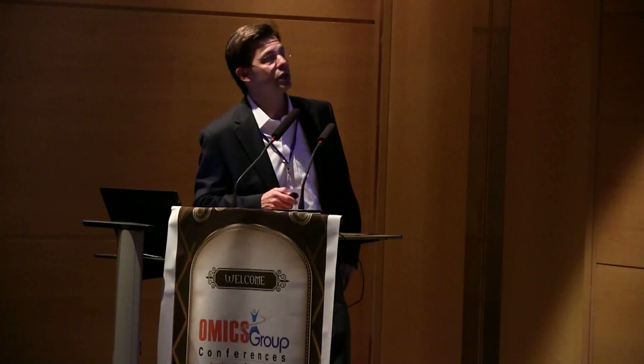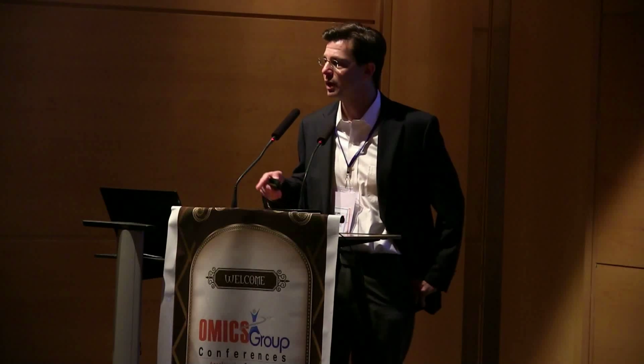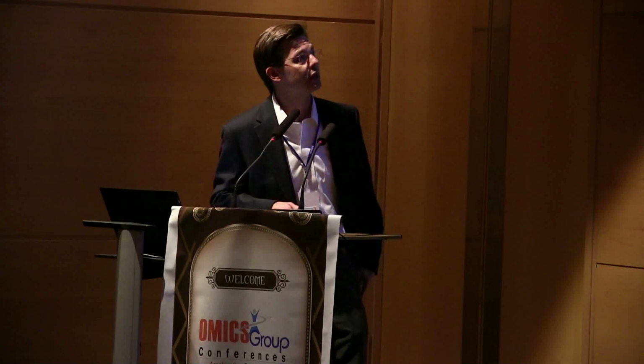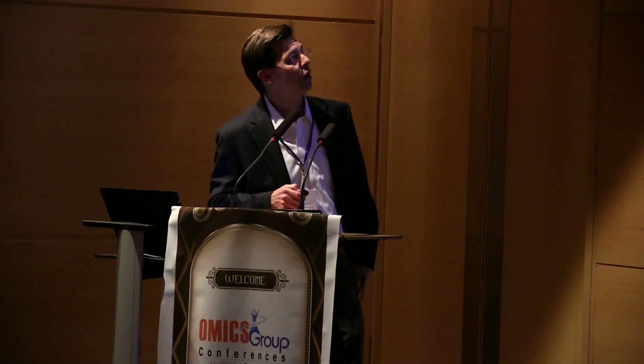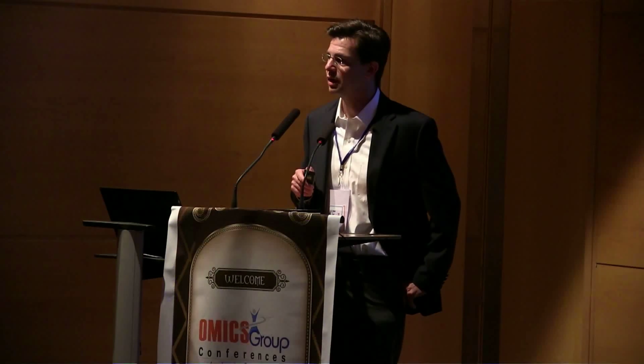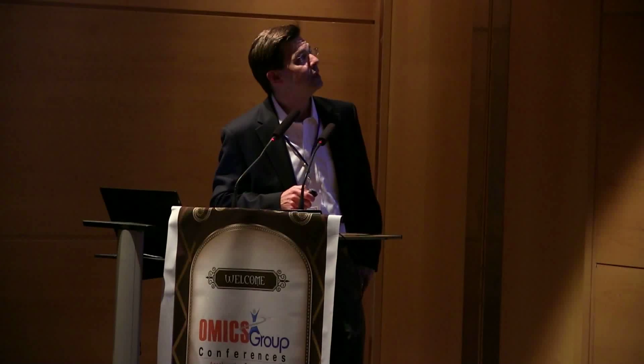So here's the Micron Jet. It's made by a company called Nanopass Technologies, and Yoram Levin is the CEO of Nanopass. We've worked closely with him in using this device in the clinic. Essentially what it's composed of is a polycarbonate hub. On the top of the polycarbonate hub, you have 3 silicon needles. These needles are made using technology from the semiconductor industry using an etching technology. These needles are only 600 microns in length.